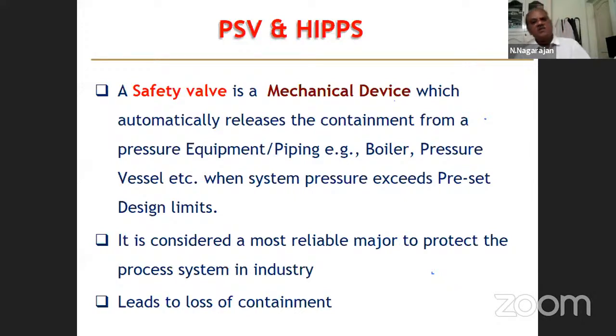As I mentioned earlier, a safety valve is a mechanical device which automatically releases the containment from the pressurized equipment or piping, for example, a boiler or pressure vessel. This releases the hazardous material to the flare system. This acts on the set pressure. There is a set pressure for the valve, which is actuated by a spring-loaded safety valve. So the spring will be lifted when the pressure exceeds the set point and opens the valve and allows the excess pressure to go to the flare. Once the pressure is relieved, then the valve has to be reset.